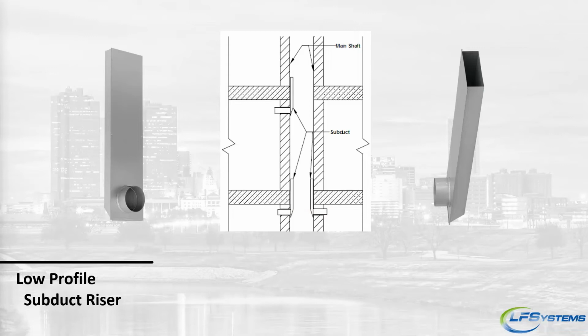using the subduct method. Now, keep in mind, this can be used for kitchens and baths as well. It's not limited to just dryers. That is the purpose of it, because you can't do the dampers. But the upside using it on bathrooms and kitchens is less maintenance, less issues with maintaining, inspections, power, all of that good stuff. So this eliminates all of that. You don't have to have access panels in your bathroom. You don't have to in your ceiling. So it really allows a lot more flexibility in your design using the subduct method.